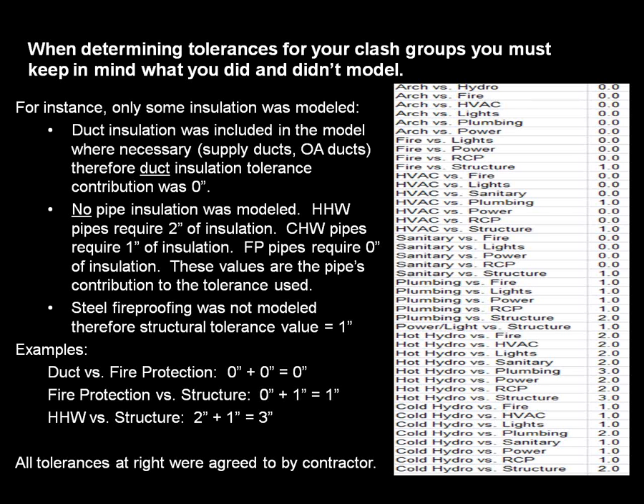Take the example of fire protection versus lights. If you had a fire protection pipe within 3 inches of a light, it would come up as a clash. But there's no reason for that, because the fire protection pipe isn't insulated, and the light has no cover on it except for the cover that's modeled.